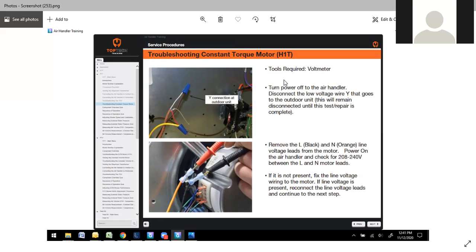That's the good thing. If you're going to troubleshoot these, basically turn the power off to the air handler, disconnect the low voltage wire Y that goes to the outdoor unit, remove the L, the black, and the N, neutral, your orange line, leads from the motor, power on the air handler, and you're checking for 208, 240 between L and N. This should be a constant power, the 208 or 240. If you have that power, your line side is good. So if it's not present, obviously you got another issue to resolve on that.